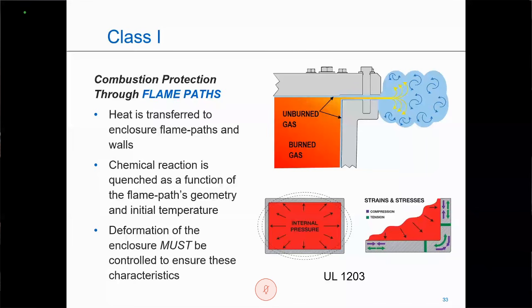Then that maximum internal pressure with a hydrostatic test is done to 4 times that original internal pressure. So we take the internal pressure from the thermal explosion and a hydrostatic test to 4 times that amount, and that gives us that 4 times safety factor to ensure that when this unit is containing an explosion, it can't rupture or fracture. And as long as the unit has been installed properly, or any maintenance, opening the enclosure and closing it back up has all been done correctly, these units can actually last decades of performance operating correctly.